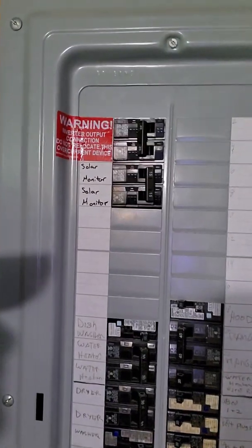So we're going to go through the troubleshooting process right now. I'm going to show you. So we're going to shut off the DC disconnect. We're going to find the AC disconnect, which this one happens to be in the electrical panel, furthest from the main backfeeding breaker. So then we're going to go back over to the inverter. We're going to let this drain down. Wait for everything to shut off.